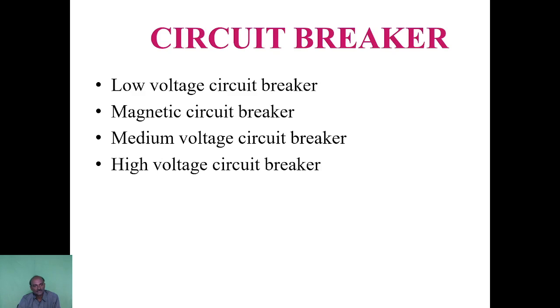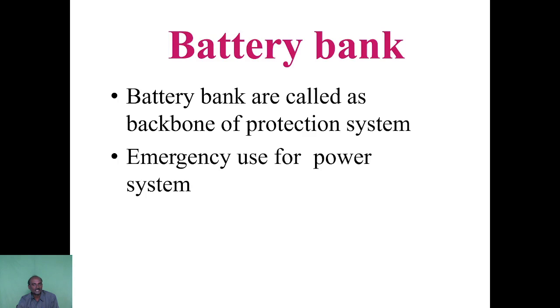Circuit breakers. The types are low voltage circuit breakers, applied in low voltage circuits, magnetic circuit breakers, medium voltage circuit breakers, and high voltage circuit breakers, based on the level of voltage where we are using them. Battery bank. The battery bank is called the backbone of the protection system. Since it is involved as a backup, it is for emergency use for the power system.